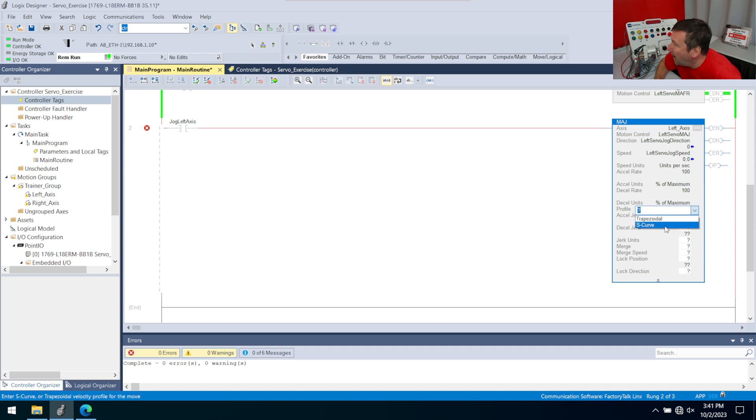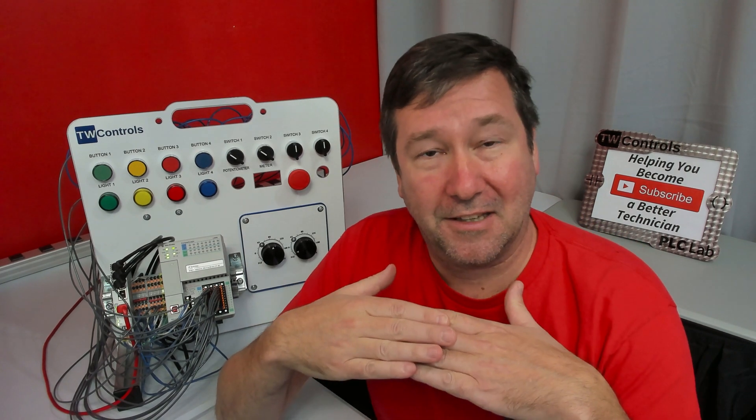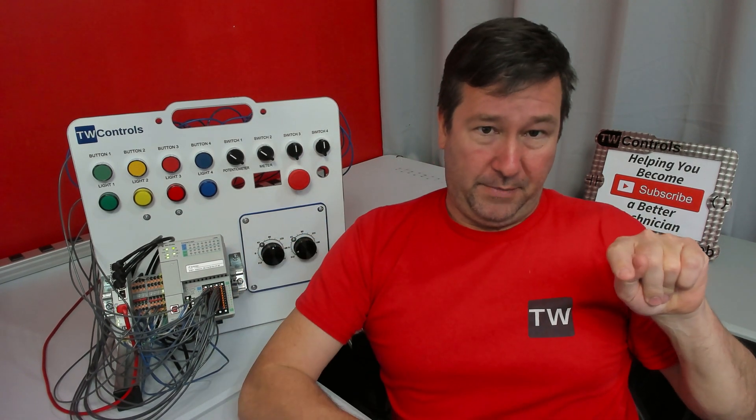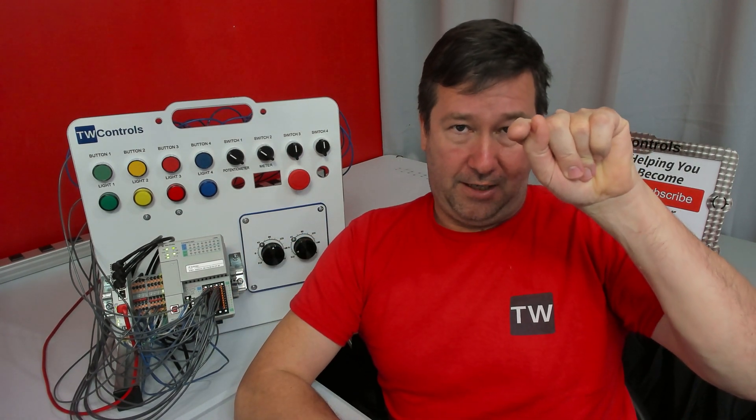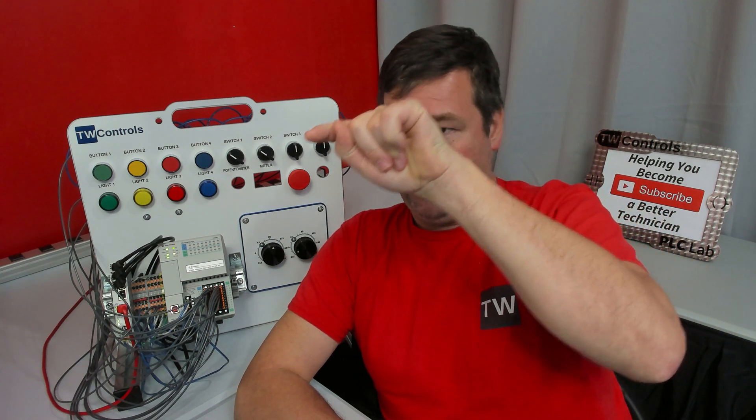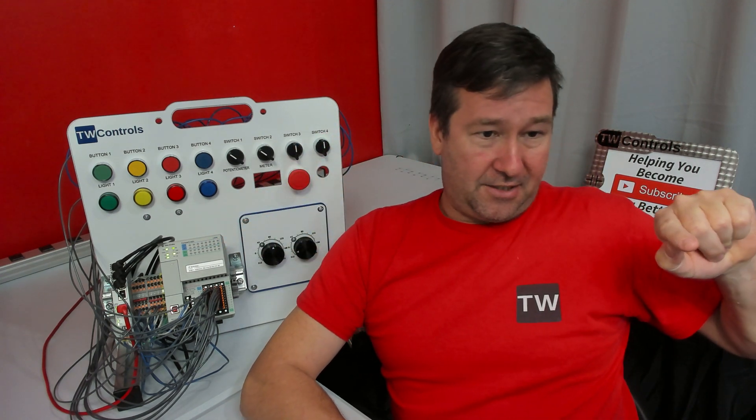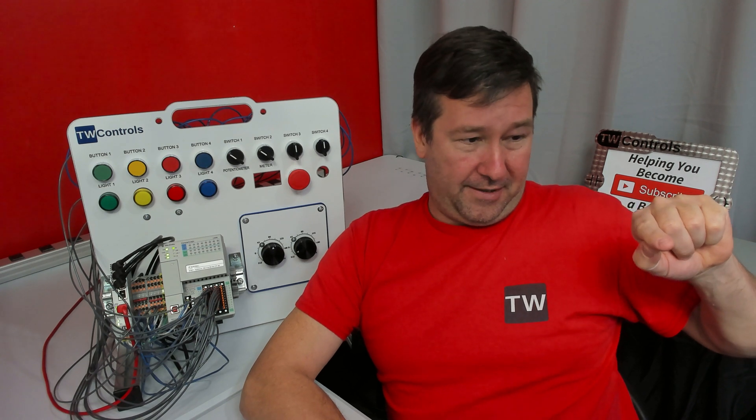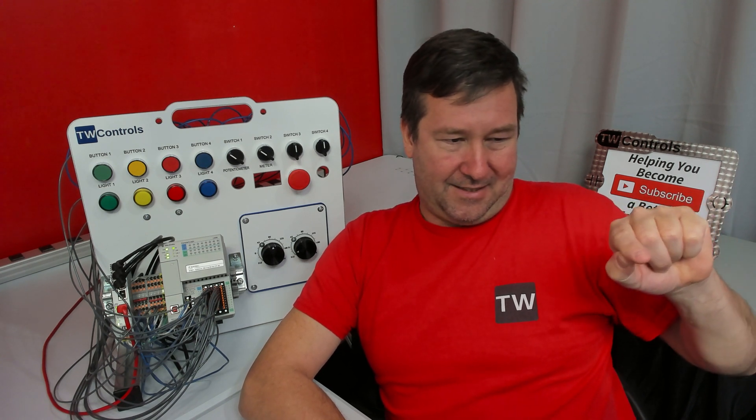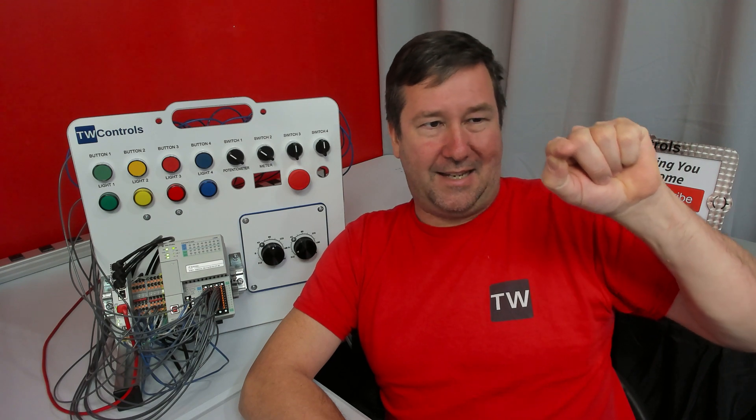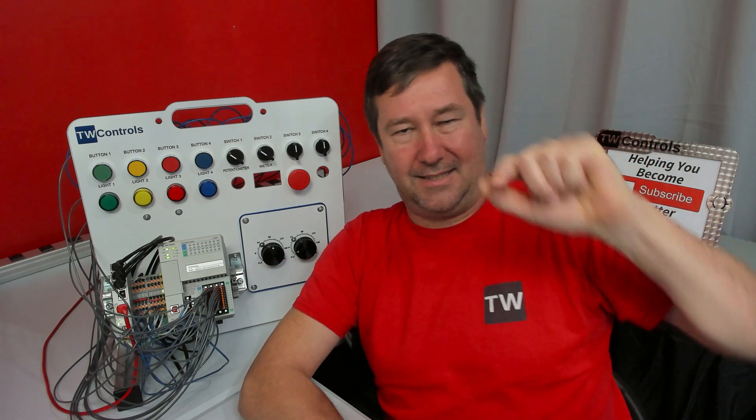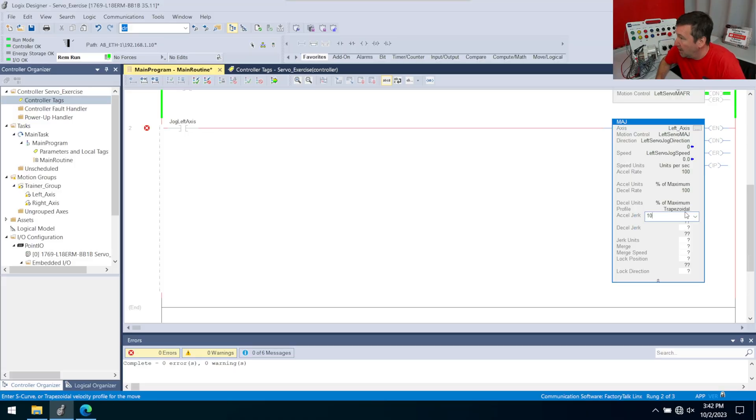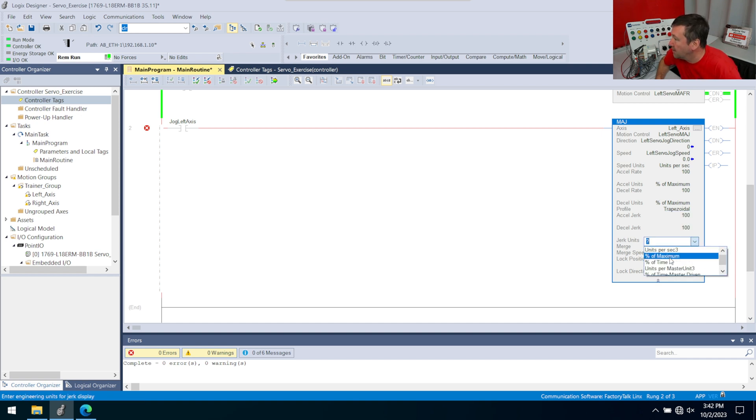Then we have a profile. We have trapezoidal and S curve. We're not going to get in the weeds of this, but trapezoidal means go directly linearly up, then we'll be steady, and then directly down. S curve kind of gives it a little easier on the mechanical part because it's going to make an S. It's going to start off a little slower, ramp high, and it's going to ease it. Instead of it going bam, bam, bam, it'll kind of just smooth it out. In this case, let's just select the trapezoidal. We have accel jerk, we're going to put 100 on it. Decel jerk, we're going to put 100 on it. Then we have our units, and we're going to put percent of maximum.